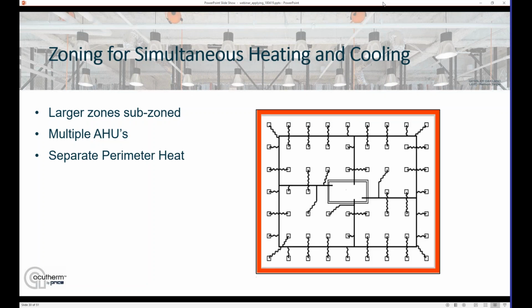Another method would be to use a separate perimeter heat system. This could be baseboard hot water, a separate ducted system. But with a separate system there, taking care of those skin losses, we can treat the rest of the building just as a single cooling zone and allow the Therma-Fuser diffusers to sub-zone that.